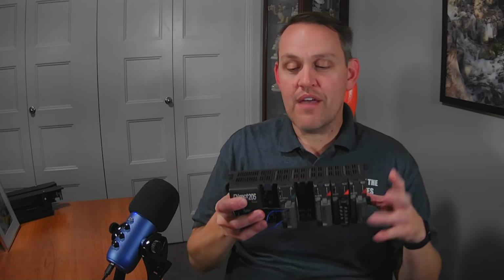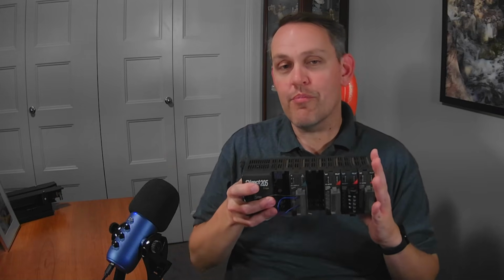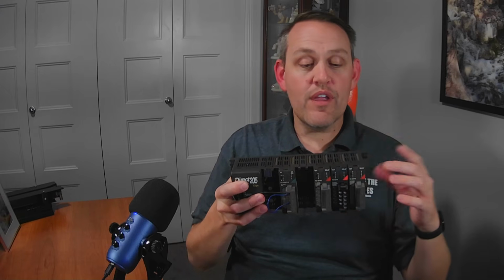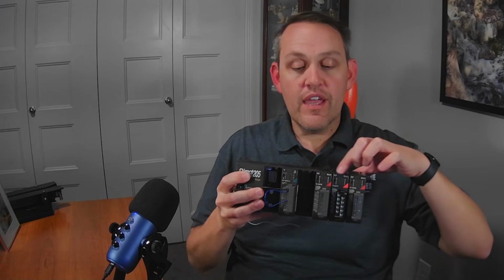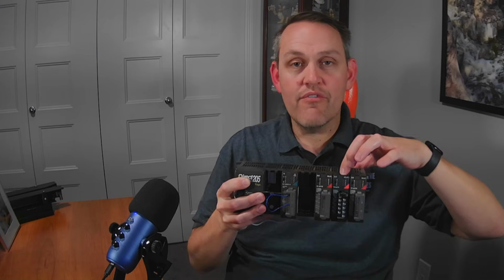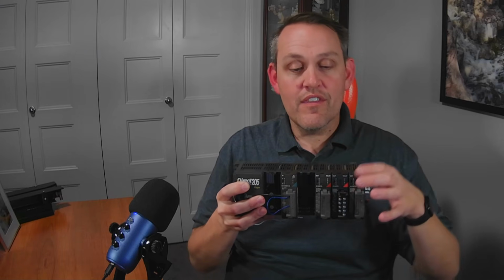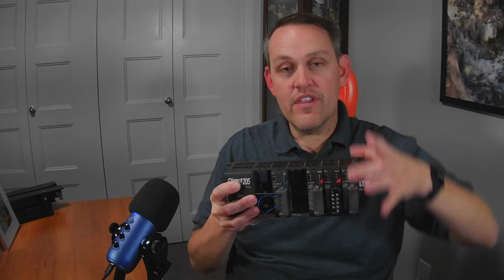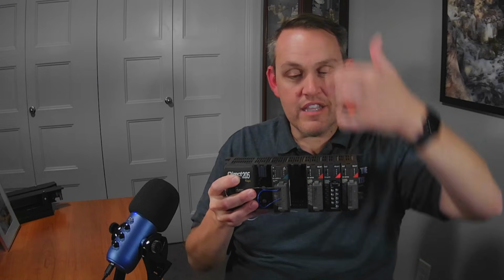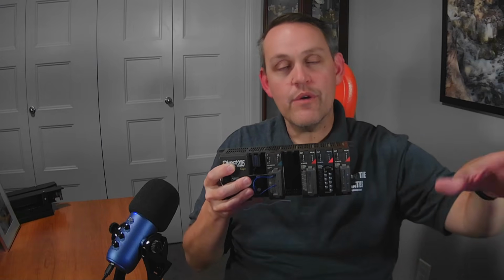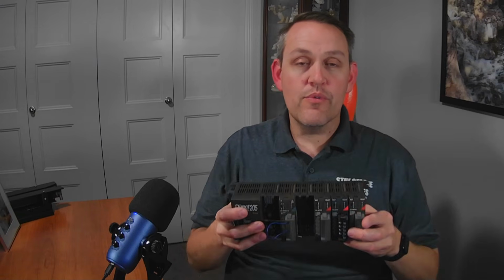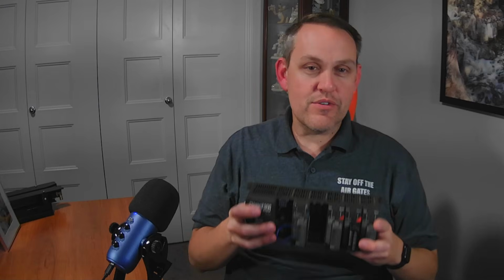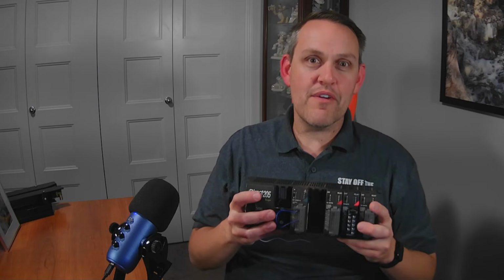Both processors have to have the same image to work properly, and then they both have to agree that they close relay output card number 5, slot 7. They both have to close 5-7 and 5-7 in order to actually let the power go through out to the ride. So these things, the processors, the safeties, and everything else get incredibly complex very, very fast.